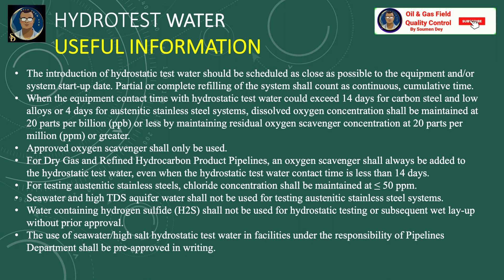For dry gas and refined hydrocarbon product pipelines, an oxygen scavenger shall always be added to the hydrotest water, even when hydrostatic test water contact time is less than 14 days. For testing austenitic stainless steels, chloride concentration shall be maintained less than 50 ppm. Seawater and high-TDS aquifer water shall not be used for testing austenitic stainless steel systems. Water containing hydrogen sulfide shall not be used for hydrostatic testing or subsequent wet layup without prior approval.